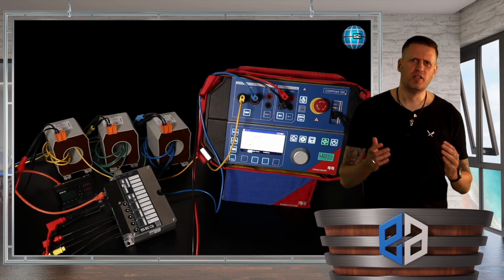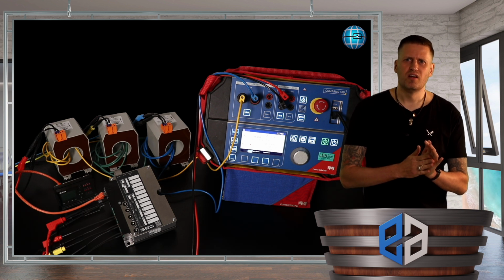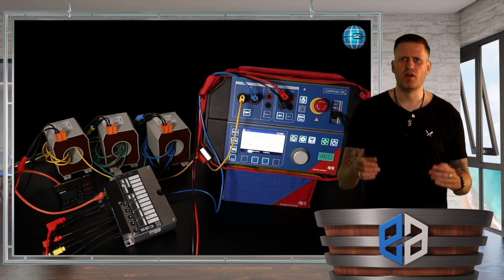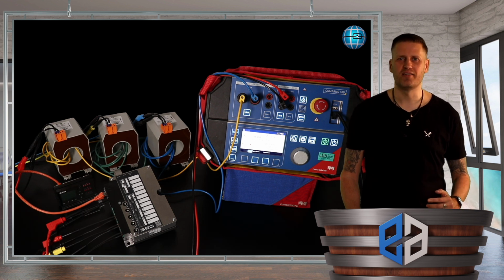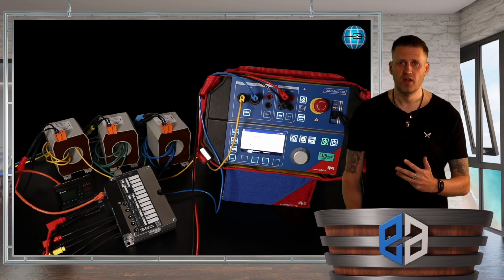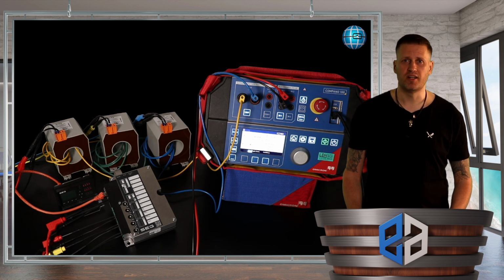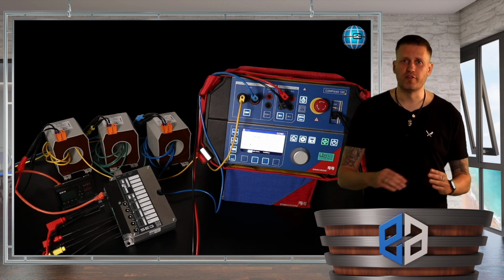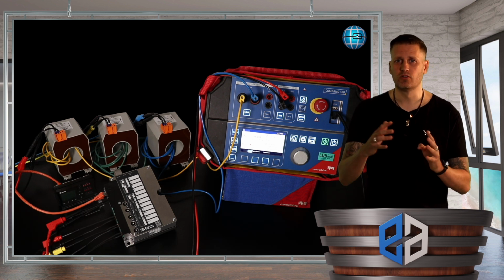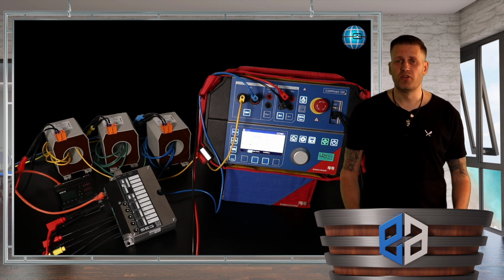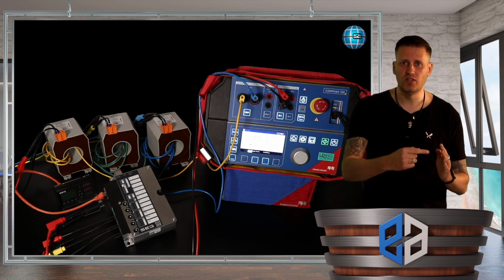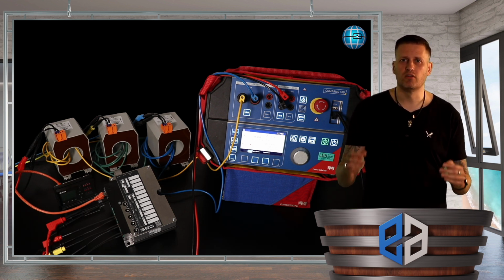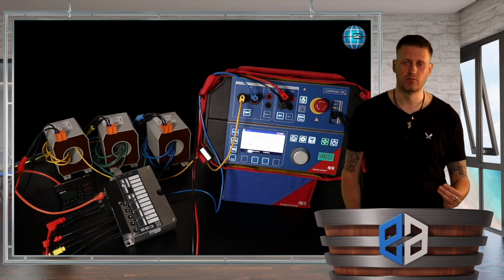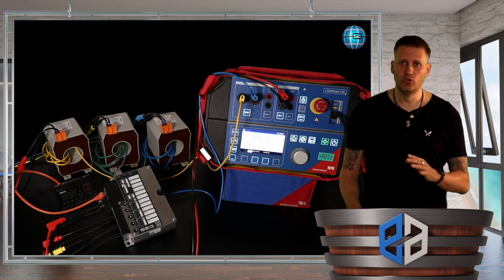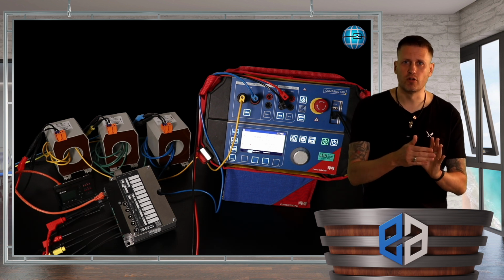We protection engineers are skeptical by nature and need to see things with our own eyes. For this reason, we have prepared the test setup shown here. We see our Compano 100 test set, which is used to drive a test current through all three current transformers. Please note that we wrapped the measuring cables 4 times around the CTs in order to avoid the test cables slipping off the table.